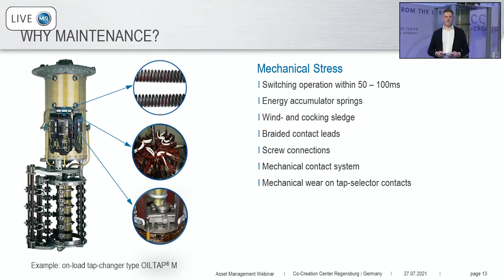As I said in the beginning, normally for network application, maintenance is just needed on external parts, so that means the motor drive unit, protective relay, and diverter switch insert. However, should you reach a high number of tap change operations, a tap selector maintenance is also necessary, where we measure the contacts or need to replace them depending on the condition.